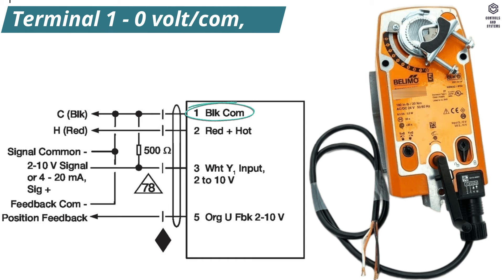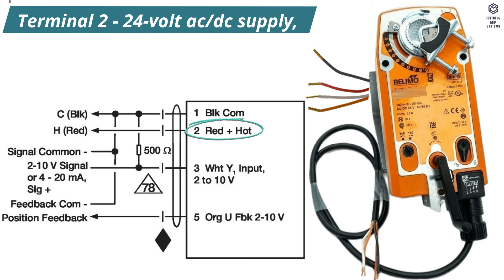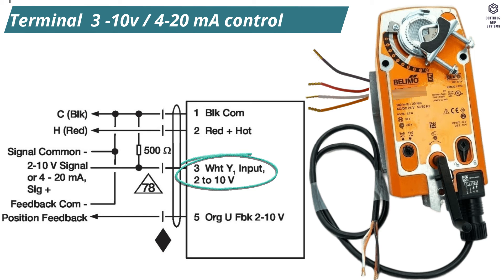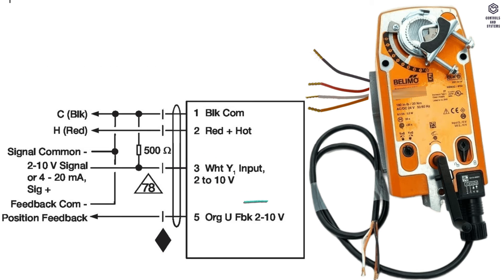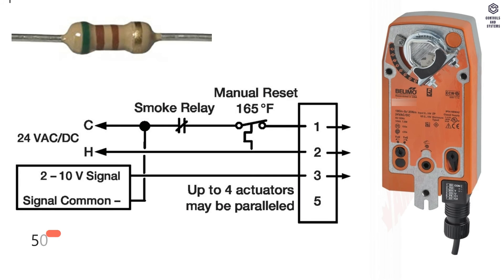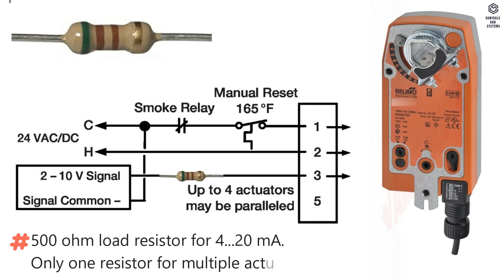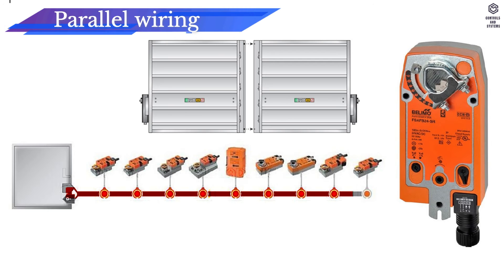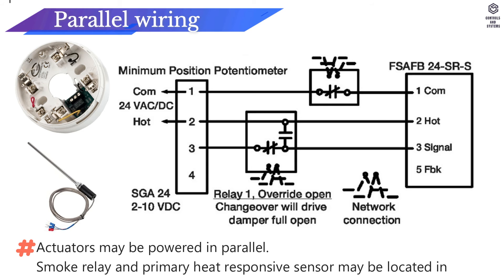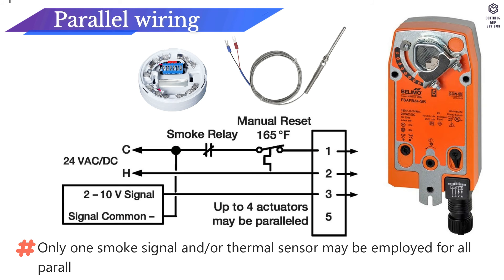Wiring data: Terminal 1 is 0 volt or common, wire color black. Terminal 2 is 24 volt AC or DC supply, wire color red. Terminal 3 is 2 to 10 volt or 4 to 20 milliamps control signal, wire color white. Terminal 5 is 2 to 10 volt feedback signal, wire color orange. A 500 ohm load resistor is required for 4 to 20 milliamps — only one resistor for multiple actuators. Actuators may be powered in parallel. Smoke relay and primary heat responsive sensor may be located in the hot wire; only one smoke signal and/or thermal sensor may be employed for all paralleled actuators.